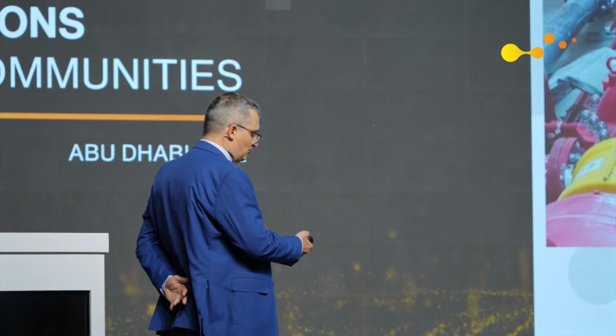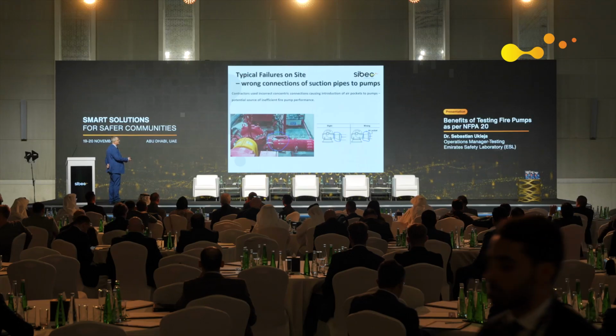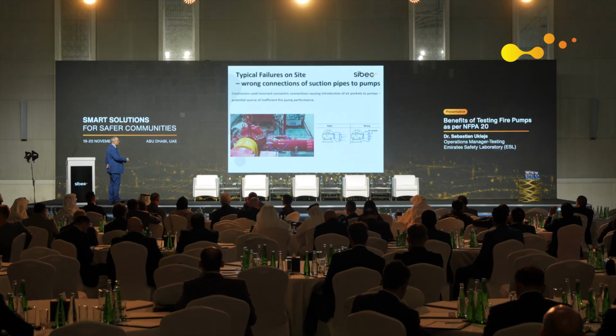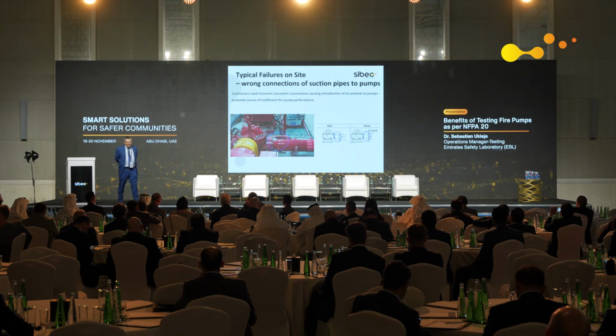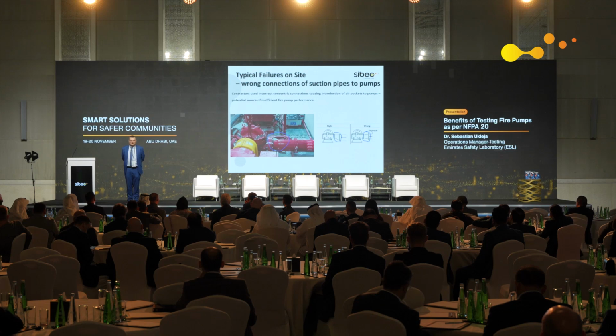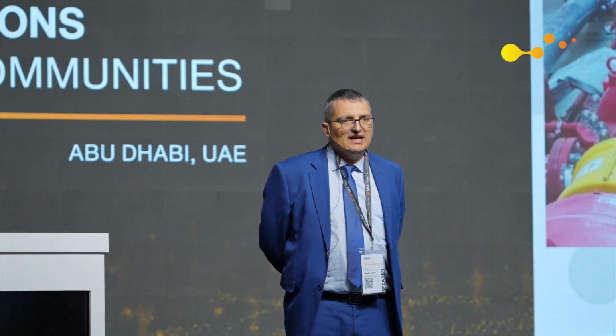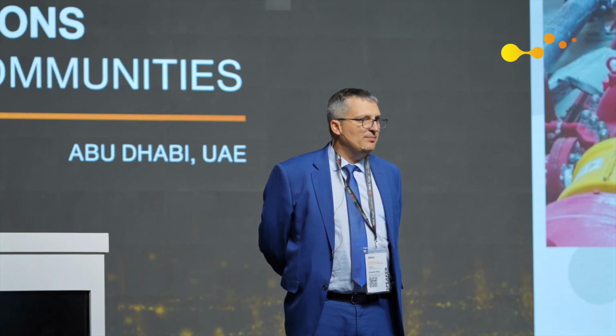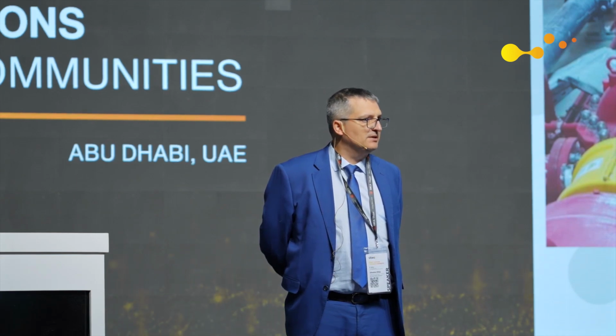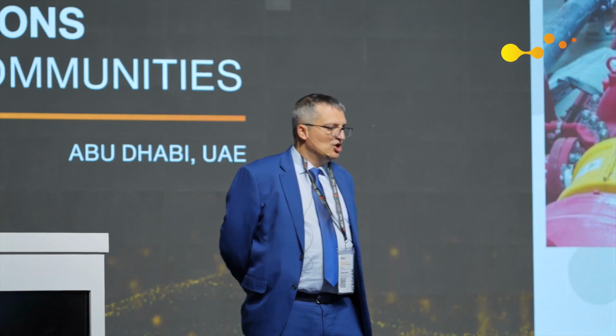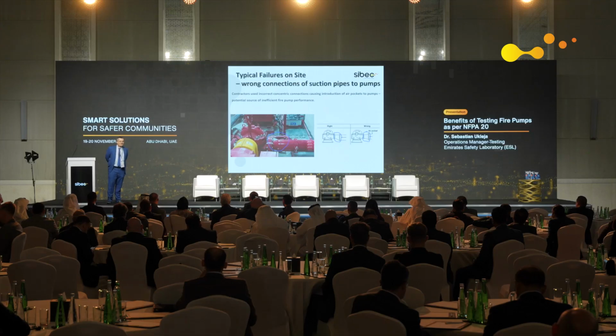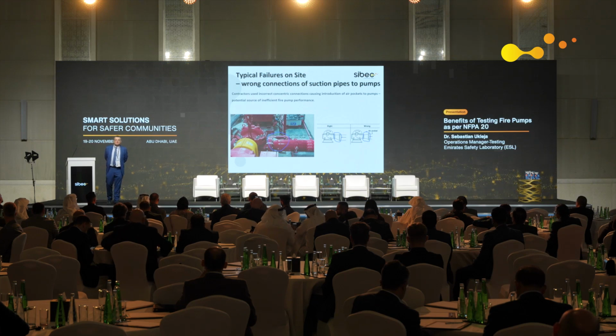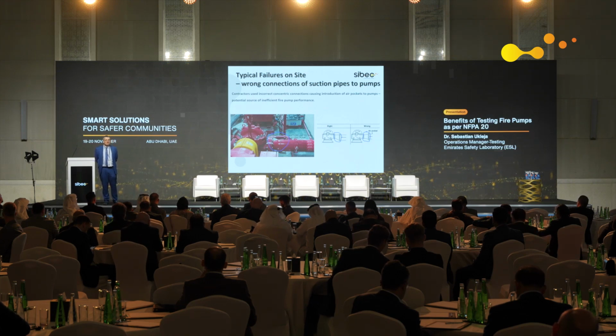Concentric installation instead of eccentric, just to explain it. This is how it should be done. This is how it's done on this photo. I saw a pump where the reduction from 8 inches to 4 inches was with this arrangement. It gives extra air bubbles or air pockets to the pump, which really affects the performance very badly, especially if there's a big reduction. So those types of failures can be really spotted not only when somebody comes and starts the pump for half an hour or 10 minutes.